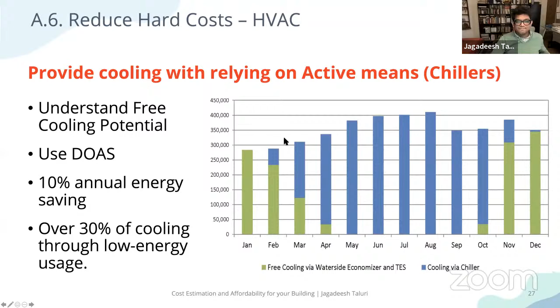Now, on reducing the hard cost, like in the HVAC, Peter also must have shown you. I'm just trying to highlight how low energy cooling, like radiant slabs, can actually cost less. Suppose in the 10,000 square meter building example I've shown you, if we were going the conventional route, we would have required 350 tons of chiller, which would have cost, let's say, 53 rupees per square foot of built up area. If you are doing radiant cooling, since you have already used all the other measures, shading, good lighting, form, mass, everything, you have reduced your heat load substantially, and your chiller plant sizing has come down to 150. Even though you're buying an expensive chiller and investing in the radiant slab, your cost per square foot for the chiller plant is going to come down.